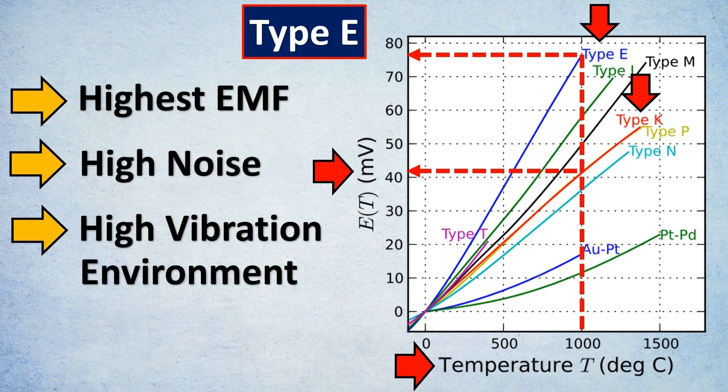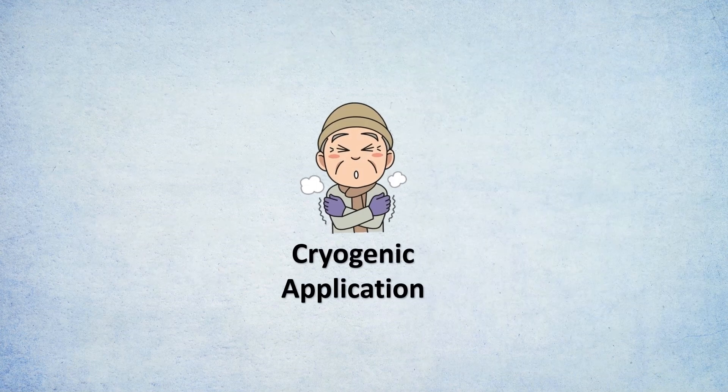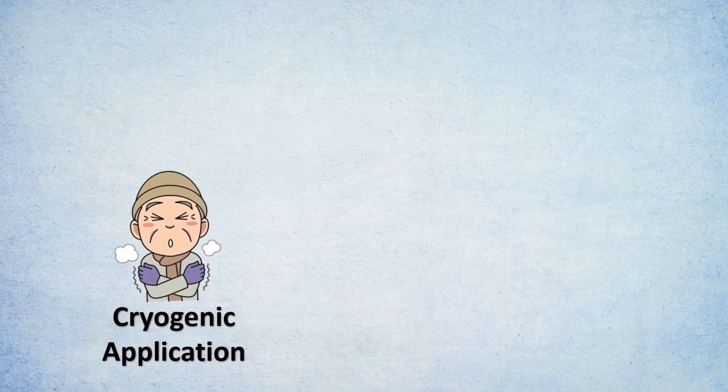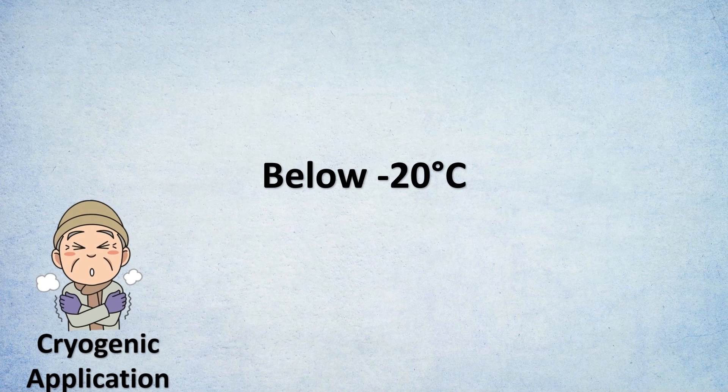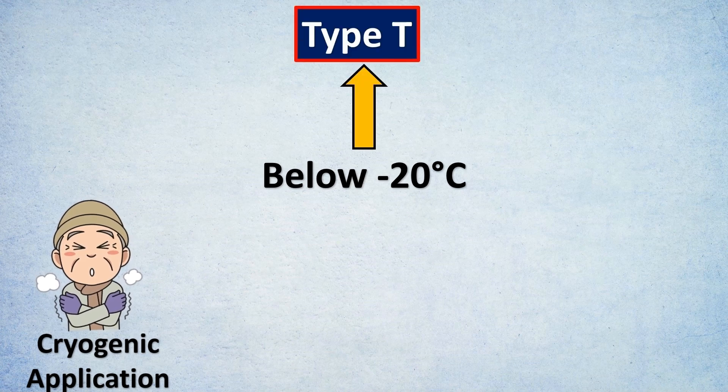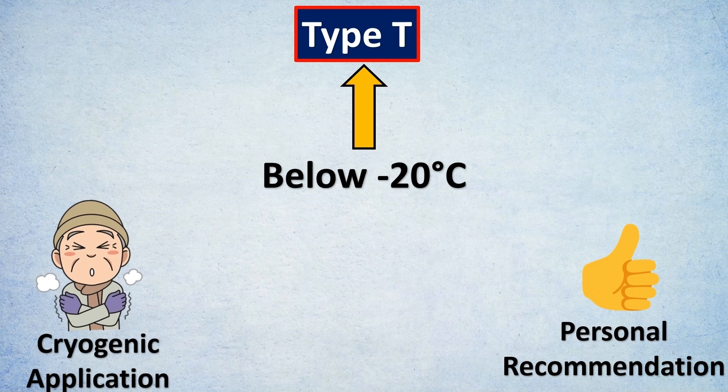In cryogenic applications, temperatures go down to maybe minus 186°C, especially with liquid nitrogen or LPG. For those cases, Type T might be a preferred choice. This is my personal recommendation based on input from various site people in terms of stability and design basis.